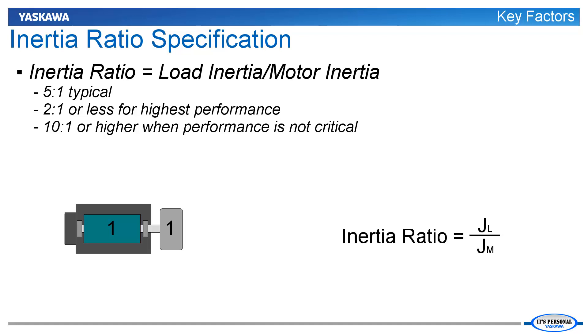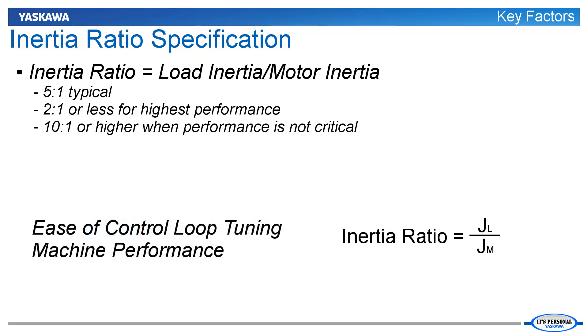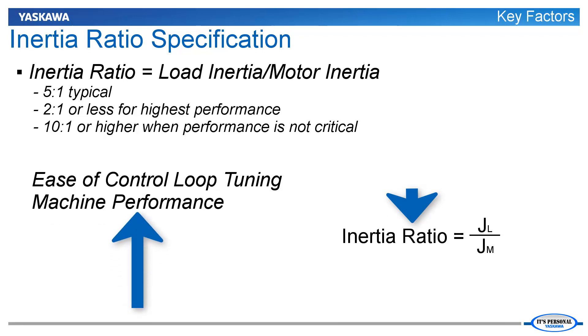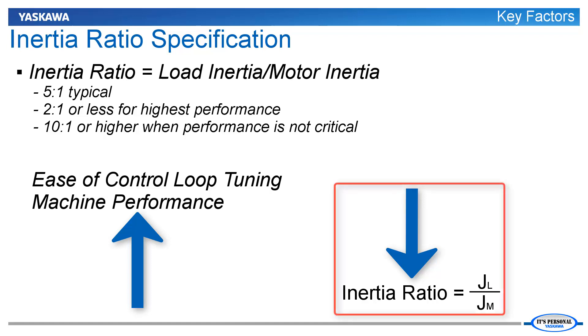However, when high performance isn't as critical, ratios of 10 to 1, 100 to 1, or even higher are not uncommon. In general, ease of control loop tuning and machine performance go up as the inertia ratio goes down. So, if all other factors are equal, a lower inertia ratio is better.